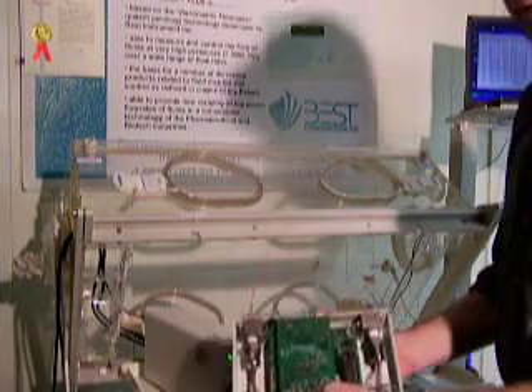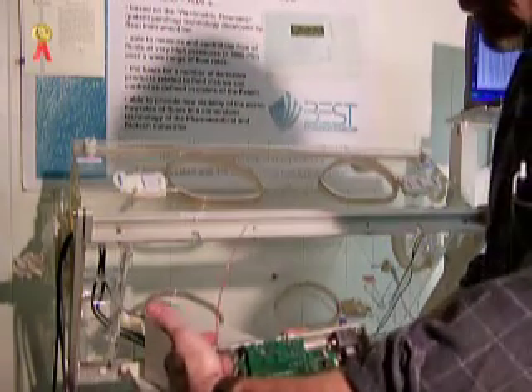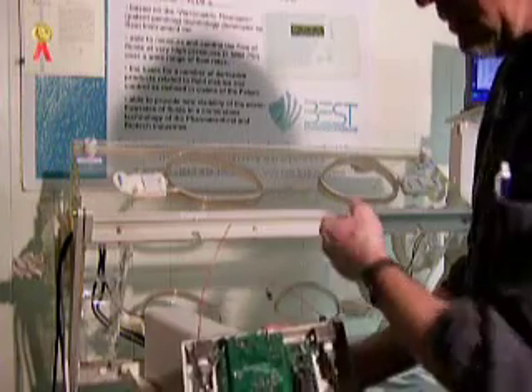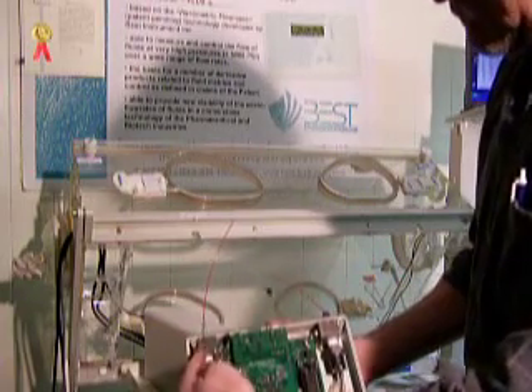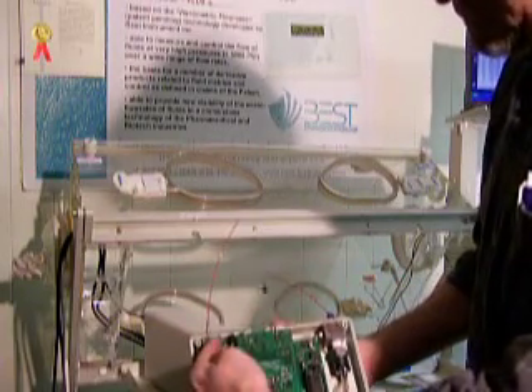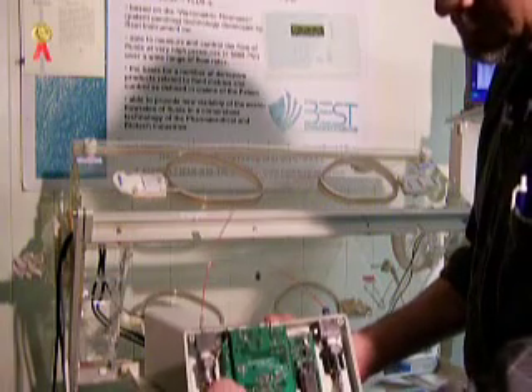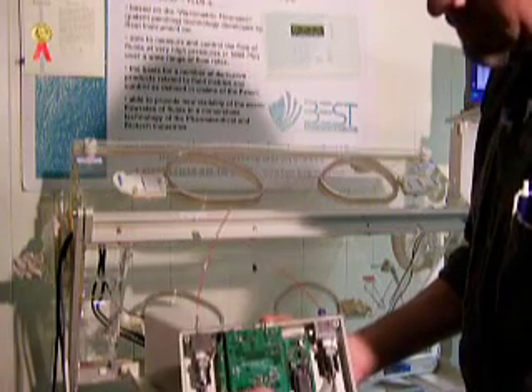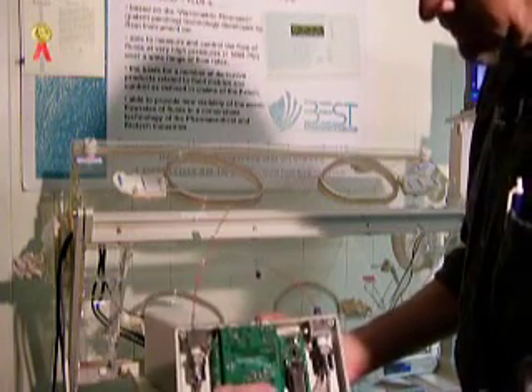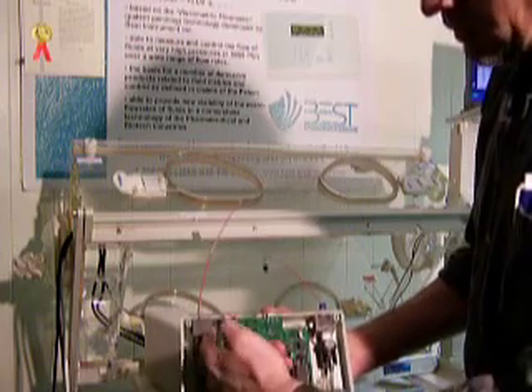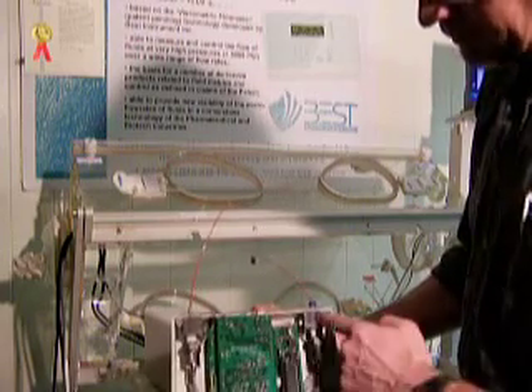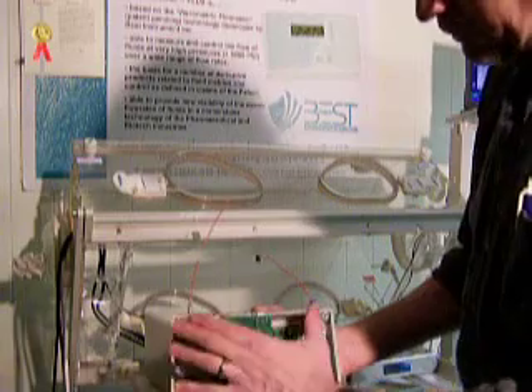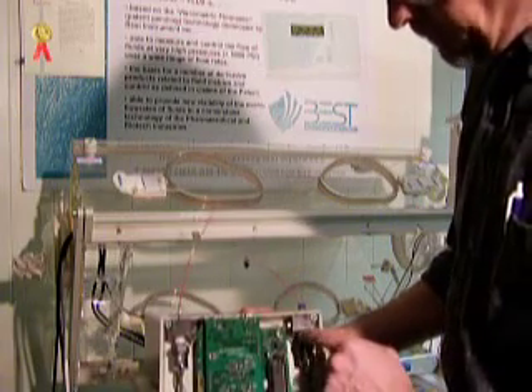Internally, we have the inlet from the outside world and the outlet. Fluids flow in where the pressure can be sensed. They then flow through this coil of, in this case, PEEK tubing, which we found later to be not quite suitable, and then through to the output transducer manifold. In this prototype, they're 3/16 stainless steel.